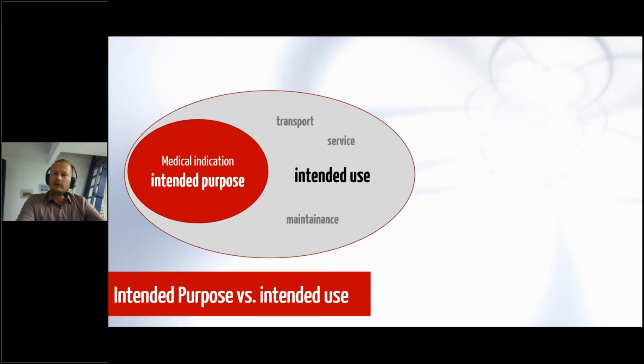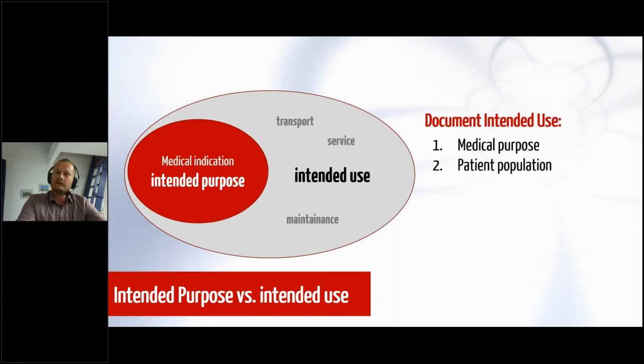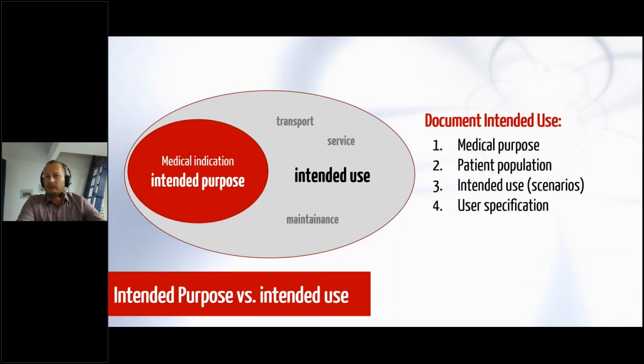So therefore, I recommend that you define an intended use document in your technical documentation, and this should define the medical purpose, the respective patient population which is targeted by the test, the intended use, so the scenarios that come along with it, and the users who are performing an action with the device during the examination.